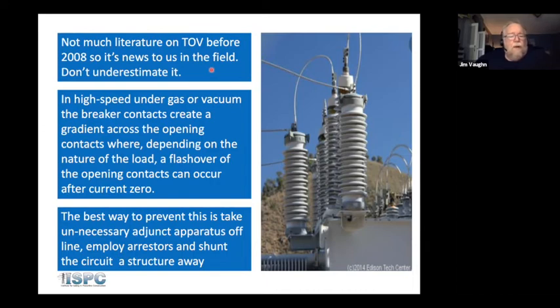The other is to employ arresters and shunt a circuit, a structure away from where you're working. We'll talk about that in a minute. Now, what the arresters can do is that if you have a TOV on the circuit, arresters, of course, can clip the voltage and send it to ground and eliminate the voltage or limit the voltage rise that occurs on the circuit. Now, over the past 10 years, I have been with some crews where they have been testing high voltage arresters and putting them on the line on transmission circuits to see how effective they are.